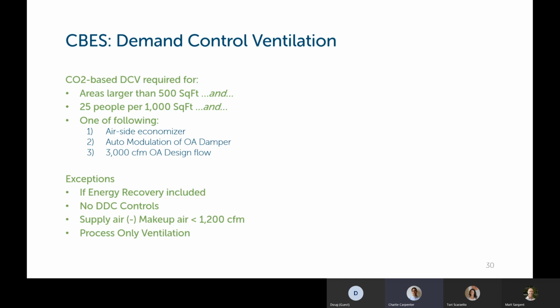Also on the ventilation side, on the commercial code, demand control ventilation will be required, that's CO2 based demand control ventilation. Any space that's larger than 500 square feet and has an occupant load of 25 people per 1,000 square feet or larger, and is served by one of these types of systems, the airside economizer system with a damper that can auto modulate the outdoor air damper, and the design airflow rate is 3,000 CFM or more. If you meet those requirements, then demand control ventilation is required for that space. As always, there's a couple exceptions listed here.